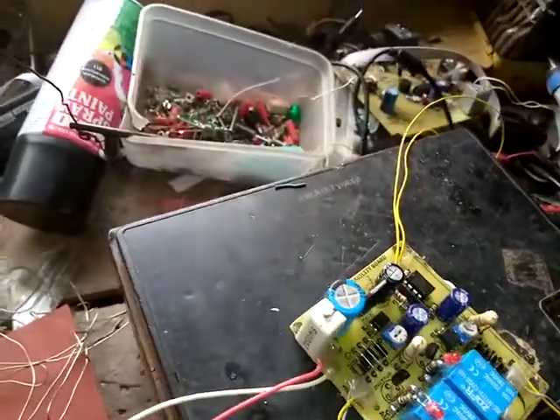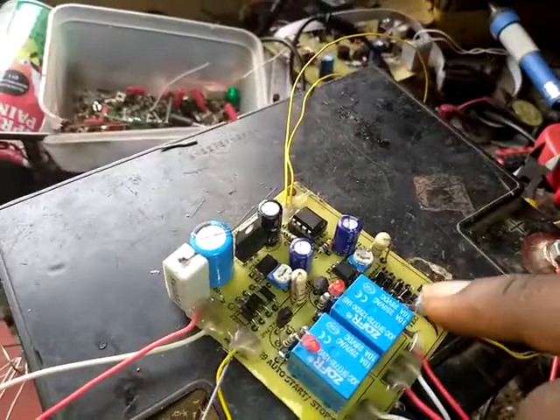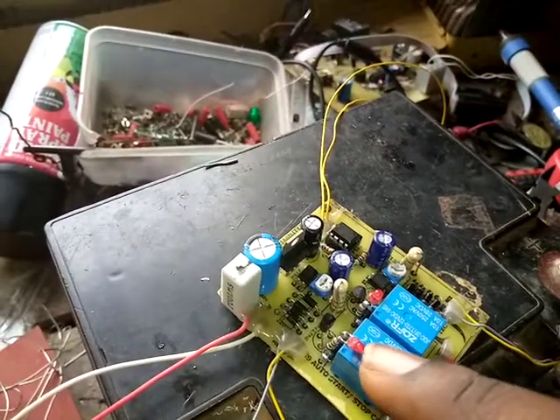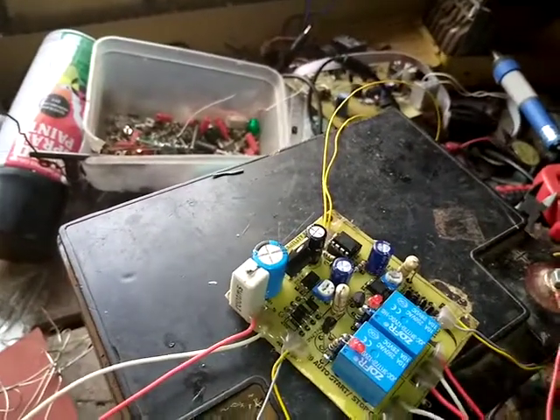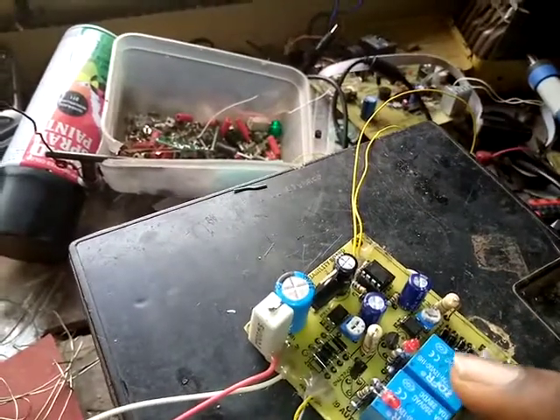We have an input voltage for the mains here and an input voltage for the generator here. Once the mains voltage is sensed, this relay will activate to stop the generator. Once the generator voltage is not being sensed while it's trying to start, it will crank the generator. Once the generator is on and sends voltage, the cranking will stop.